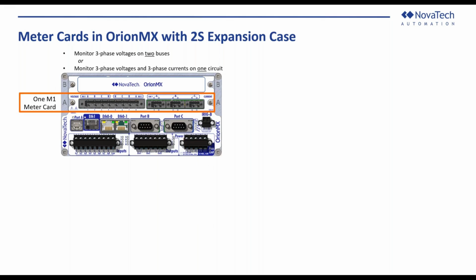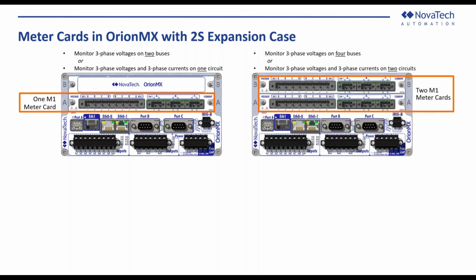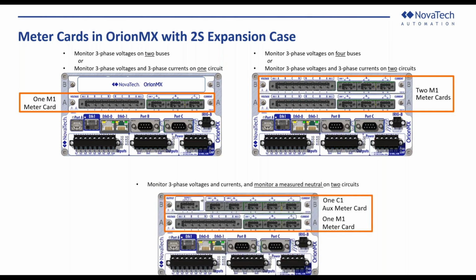See what these look like in the case. There's one M1 meter card in the case. That's good for monitoring three-phase voltages on two buses, or three-phase voltages and currents on one circuit. And you can put two of those into a 2S case. And next click. This is a combination of the M1 and C1 card, as we mentioned before, three-phase voltages and currents, and a measured neutral on two circuits.